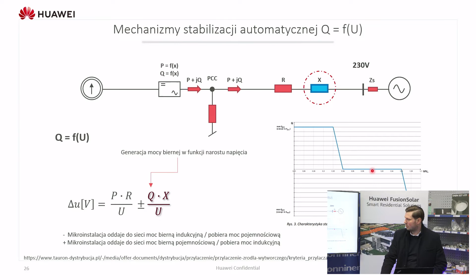This characteristic curve, where the output reactive power depends on voltage, will look like this. Here we have 230 volts, and when the voltage is rising, the inverter tries to generate some reactive power with a minus sign, so the total voltage difference will be reduced. This is the solution to the problem.